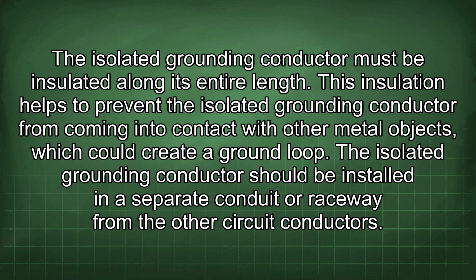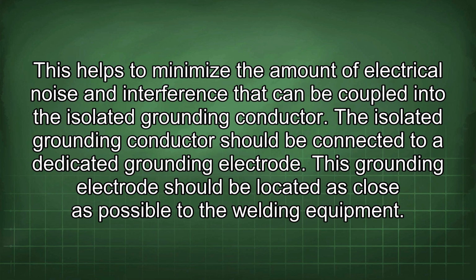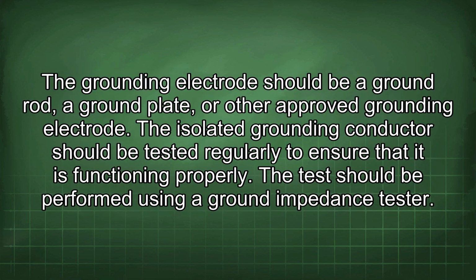a ground loop. The isolated grounding conductor should be installed in a separate conduit or raceway from the other circuit conductors. This helps to minimize the amount of electrical noise and interference that can be coupled into the isolated grounding conductor. The isolated grounding conductor should be connected to a dedicated grounding electrode. This grounding electrode should be located as close as possible to the welding equipment. The grounding electrode should be a ground rod, a ground plate, or other approved grounding electrode.